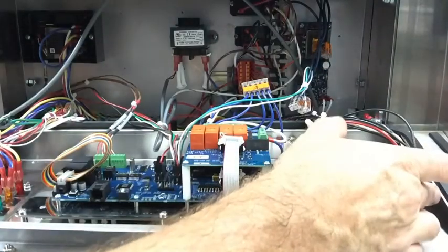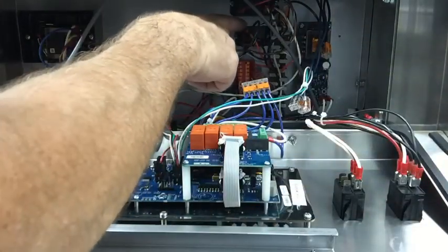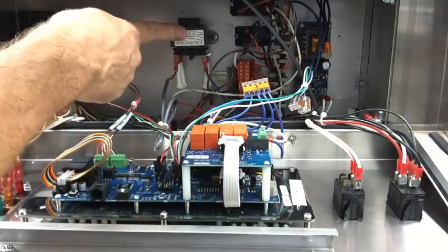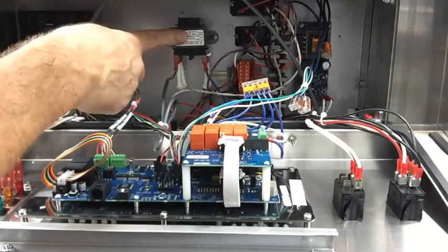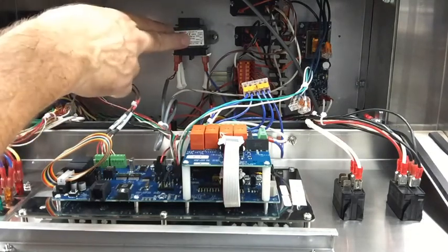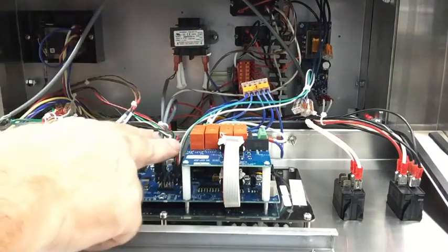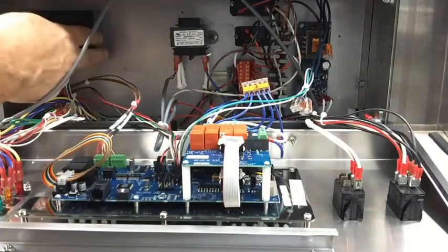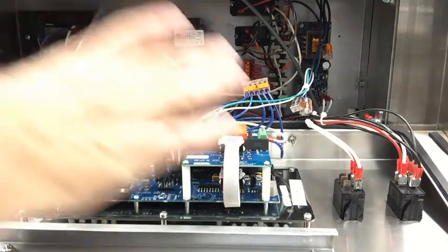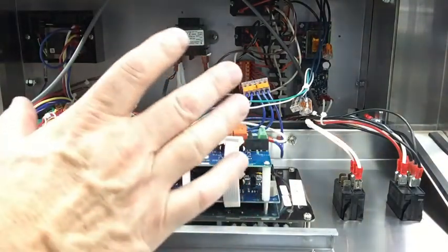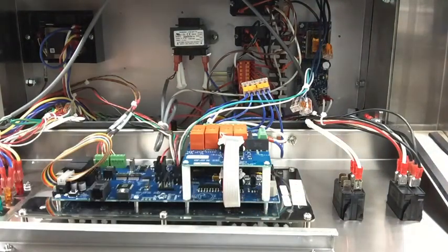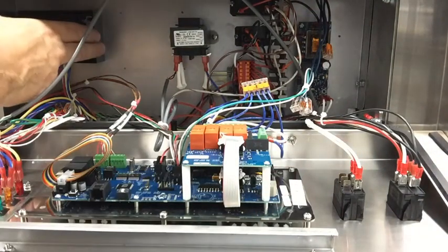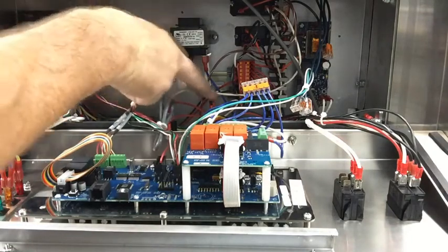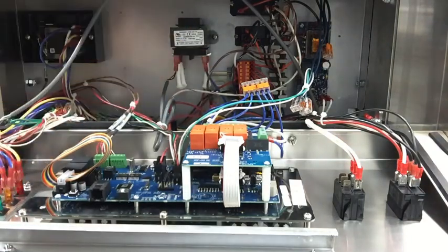Your terminal blocks. This is your relay. When you energize this switch right here, your power switch, it'll pull in this relay. It's a power relay, sends power to the terminal blocks. This transformer is a 208 to 18 volt transformer. It's taking the 208, turning it down to 18 volts for your controller. This is your high limit board. It's totally separate from your controller. In case something goes wrong with the controller, you want it to be independent, so it'll still catch that high limit, 450 degrees. You've got two fuse holders right down here in the center, and that's pretty much it.